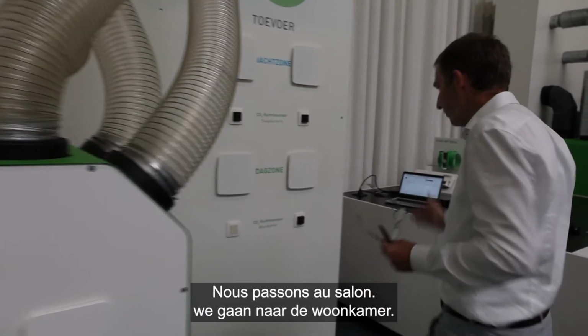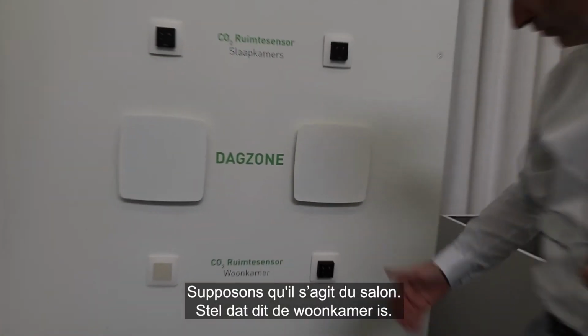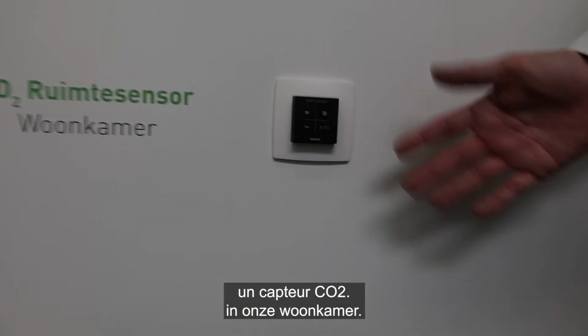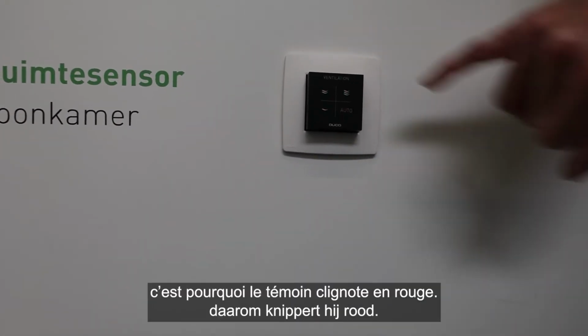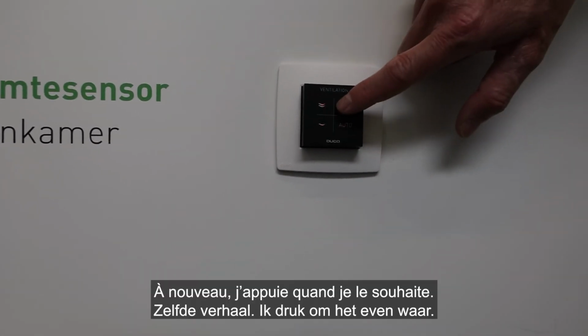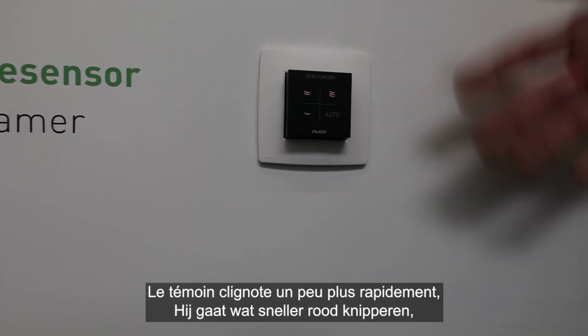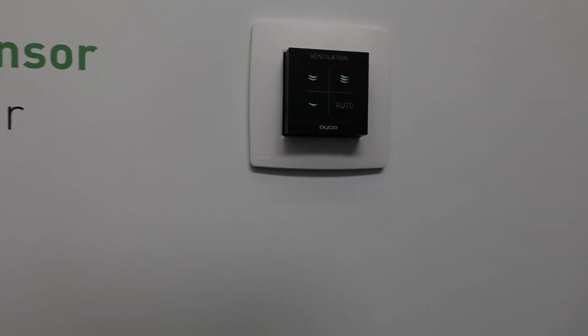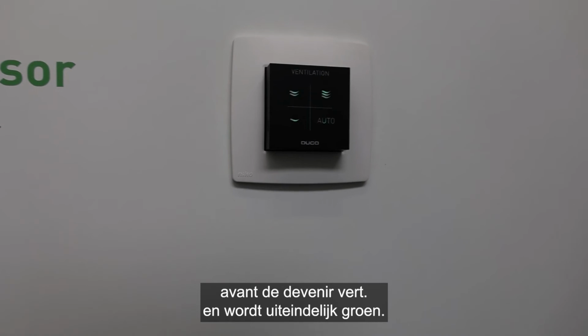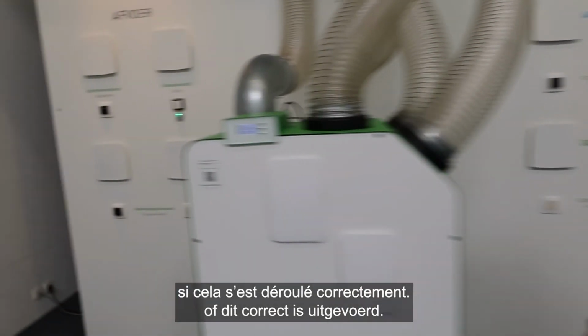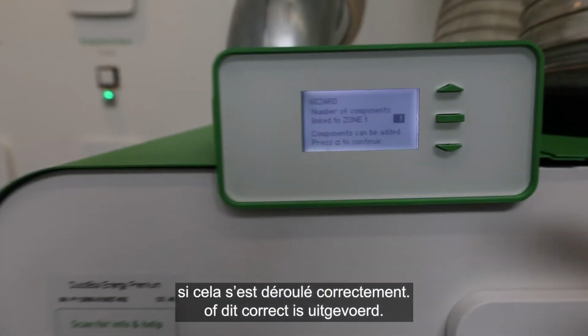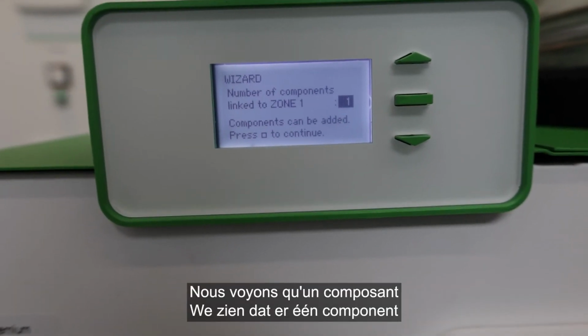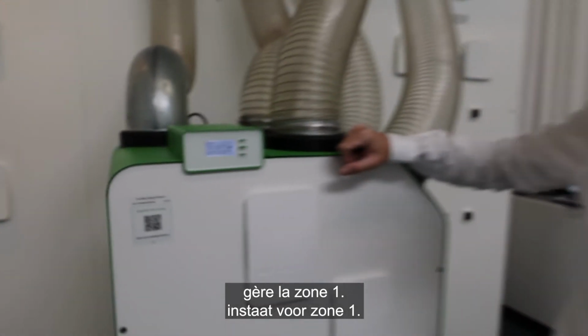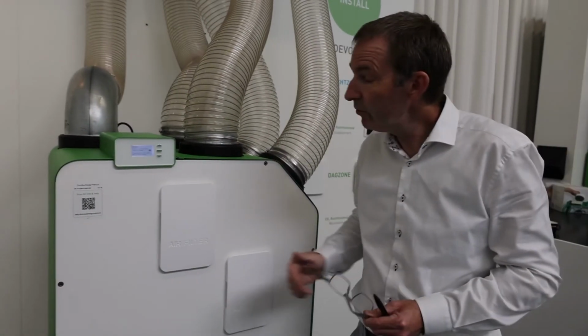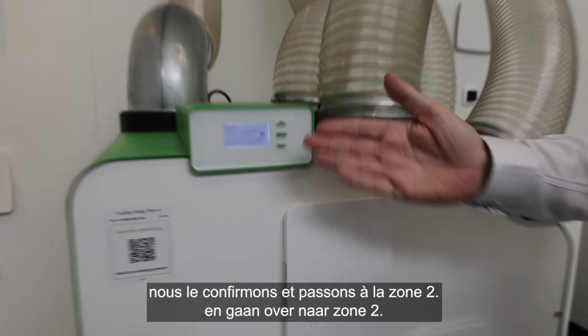Zone 1, we move to the living room. Okay, suppose this is the living room. We have a CO2 sensor in this particular living room. It is live. Okay, this is why it is blinking red. Again, I push wherever I want to, it's blinking red a little bit faster, and ultimately it will turn green. Voila, there it goes. We go back to the machine to check whether this has been executed correctly. Yes, indeed, we see that one component is in charge of zone 1. And now, logically, we confirm this, and we go to zone 2.